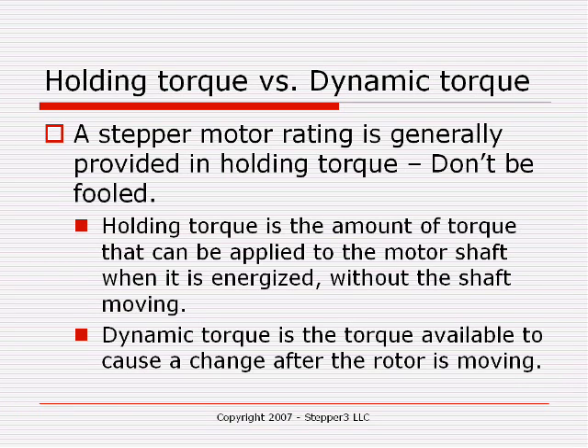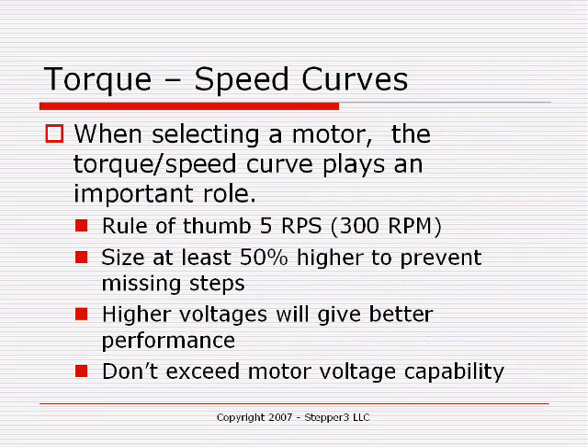Dynamic torque is different — that means you're already moving and need to accelerate or decelerate. The dynamic torque is not 260 ounce-inches even if that's the holding torque rating; it's generally much less than that. You need to go to the torque speed curves to determine what amount of torque is available at a specific speed. There are a couple of rules of thumb.